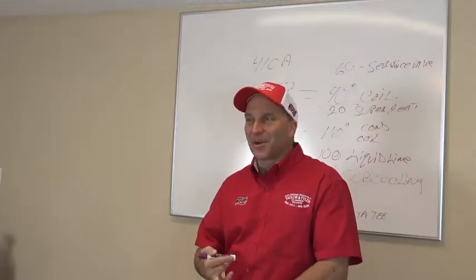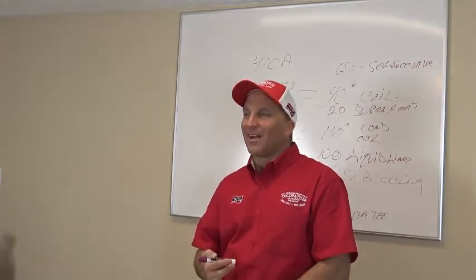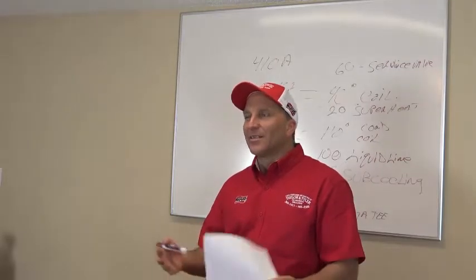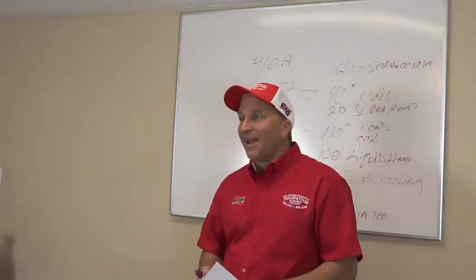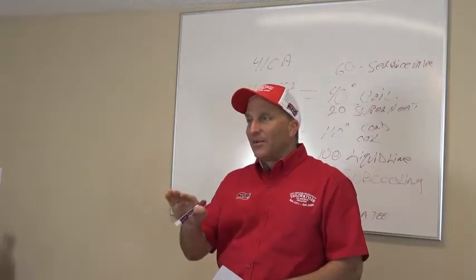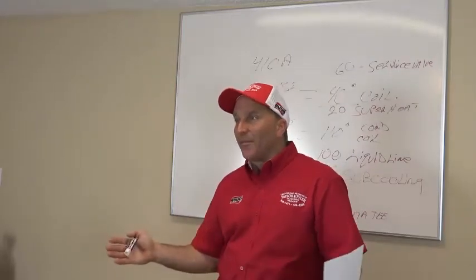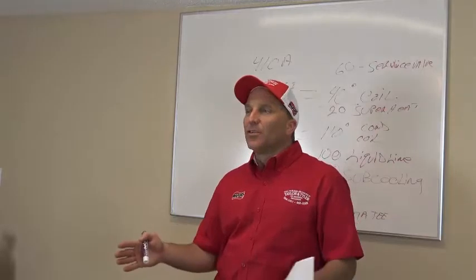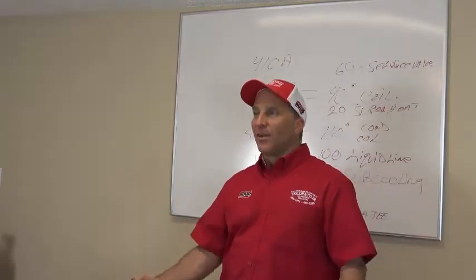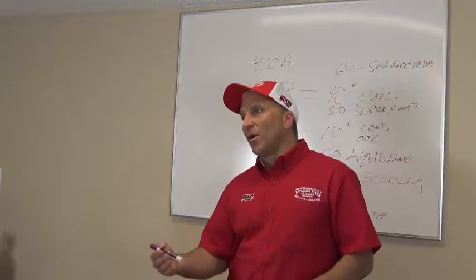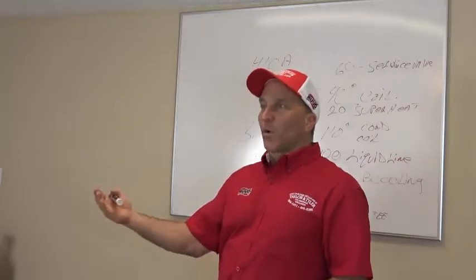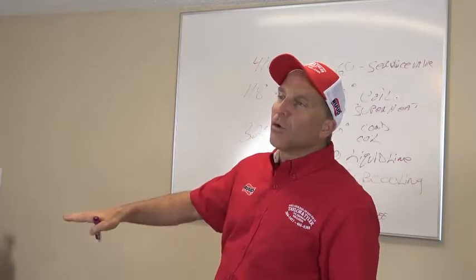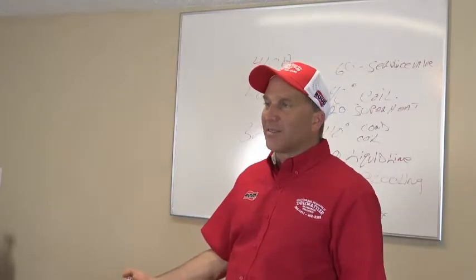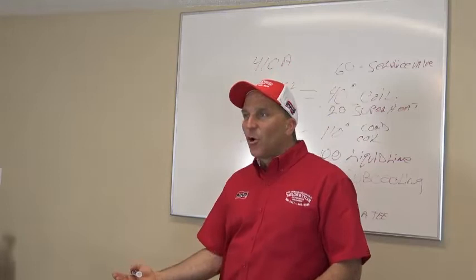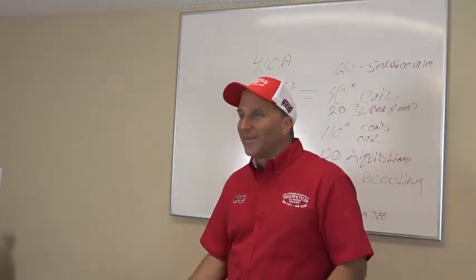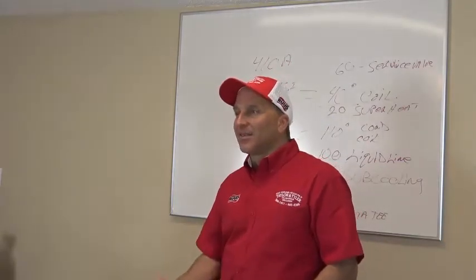He had a single-stage thermostat, and was wondering why he never had a lot of airflow out of his vents, and why his energy bill was always $400. Because heat strips were constantly running. No, because he had single stage running all the time. Right. So what happens when you have single stage running all the time, the system never shuts off and never really reaches its point where it can shut off. I'm still running a 4-ton compressor, but it's got an unloader in it, and I'm only running 2.5-ton capacity. So while it would cool, it never would cool great because I never would kick in second stage.